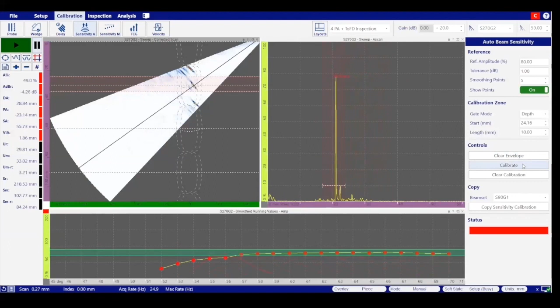So using WeldSight for doing these calibrations makes it much easier because of the faster refresh rates, based on your computers and everything. But we also have a status bar. Once the calibration is within the tolerances we have set, which is the 80% plus 1 dB of tolerance, we can see the status bar changing into green.